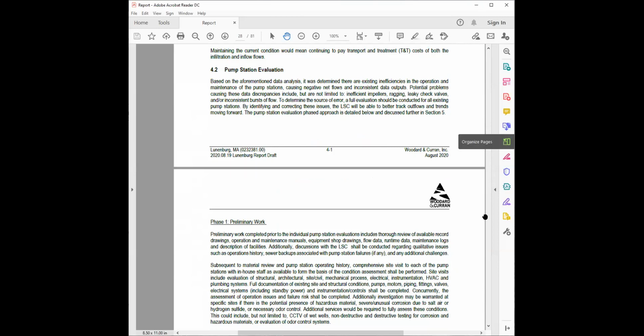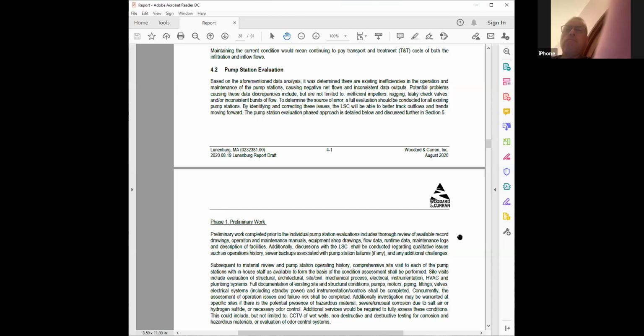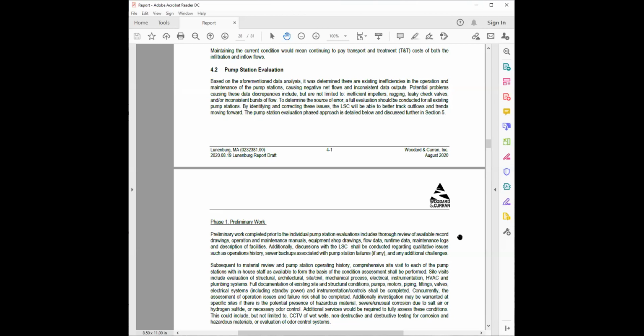There could be a few potential issues, and it's hard to pinpoint when we don't really know what's going on at each of the pump stations from our end and perspective, but there could be some potential inefficiencies in the operation and maintenance of these pump stations, so that could be causing the negative net flows. You mentioned check valves, so we could have some leaky check valves. Pete has a bit more knowledge on this regarding inconsistent bursts of flow, which could skew those weekly pump station logs we're getting, causing overlap and those negative flows. That corresponds to inconsistent data outputs, or we could have inefficient impellers or ragging. If that's a known issue in the past, it could still be continuing.